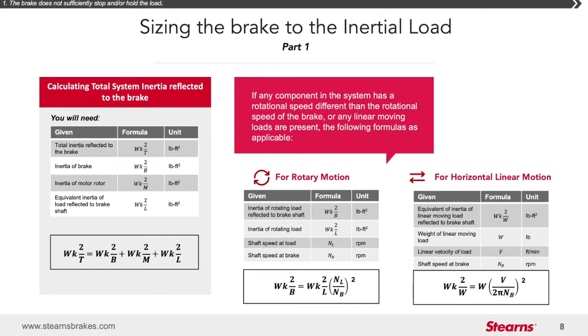Torque and power reduction can be significant in the case of vertical linear applications. The main purpose of a holding brake is to relieve the motor from maintaining the holding torque during standstill periods in vertical linear motion applications. For horizontal linear applications, the total torque of the application will be zero during motor standstill, and the motor does not need to maintain holding torque. Therefore, a holding brake may not be necessary. The final decision to apply a brake should only be based on calculating the torque requirements.